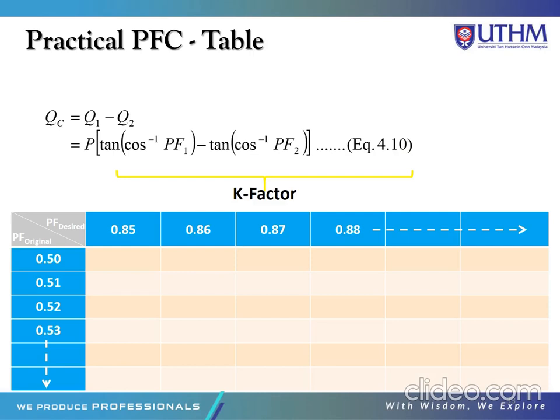This is the practical PFC table. We have to calculate the QC by using this formula. QC is the Q that will be installed to improve the power factor. PF1 represents the power factor original, and PF2 represents the power factor desired. So we can calculate the values and put all the QC in the table.